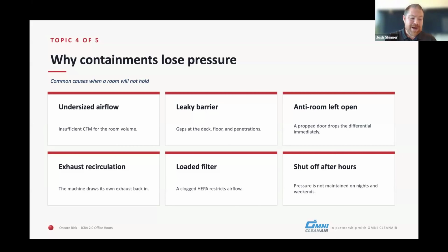Number two, I agree, leaky barrier is a huge one. It's one that's underinvested, and that's the one that we tend to get the mysteries from. When you talk about the smoke test, your covered vents is such a story that we've taken to heart. We had contractors saying, 10 o'clock every night, the alarms are going off. What's going on? Why do we keep seeing this happen? And then we're looking at the trackable report and we see it going. Well, sure enough, there's a leak in the roof containment. Usually the AC machine is shutting off or turning on at that time, and that's what's causing it. And they didn't do a great job of covering those vents.